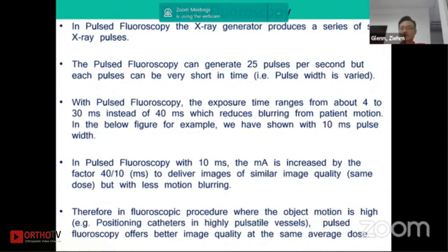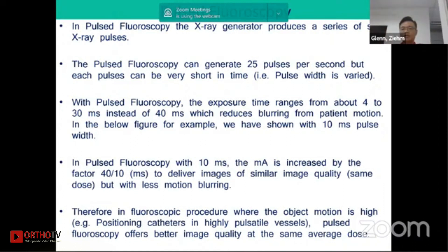In pulse fluoroscopy with 10 milliseconds, one pulse is 10 milliseconds. The mA is increased by a factor of 40 over 10 milliseconds to deliver images of similar image quality, having the same dose but less motion blurring. In fluoroscopy procedures where object movement is high, pulse fluoroscopy still offers better image quality at the same average dose.